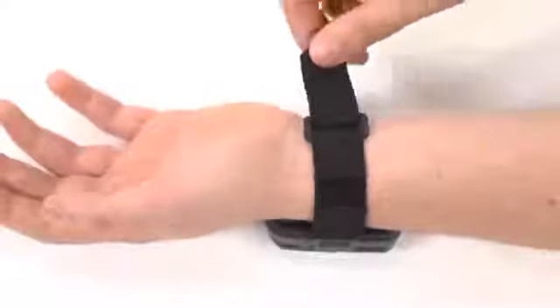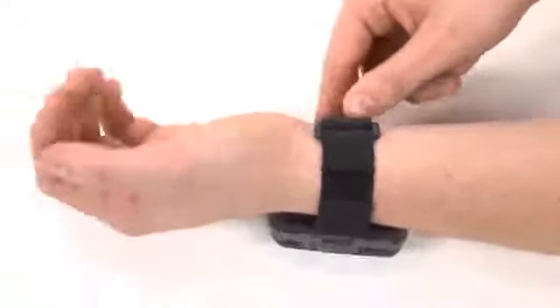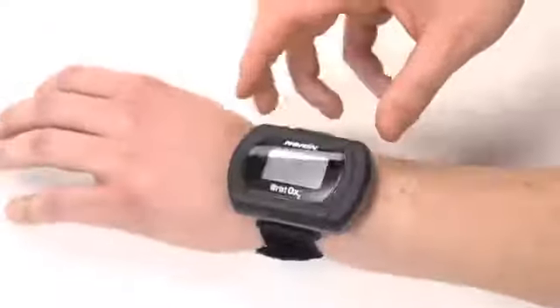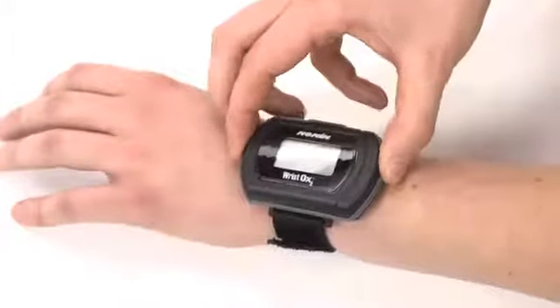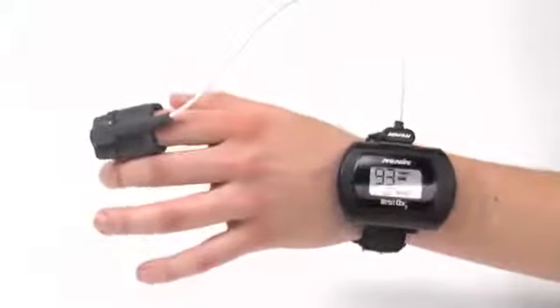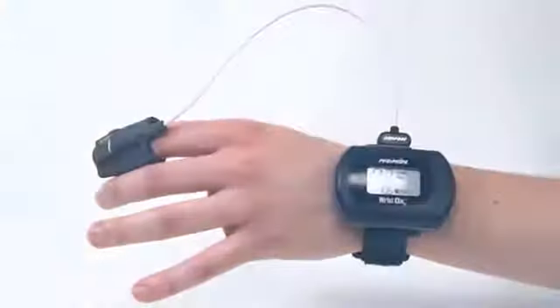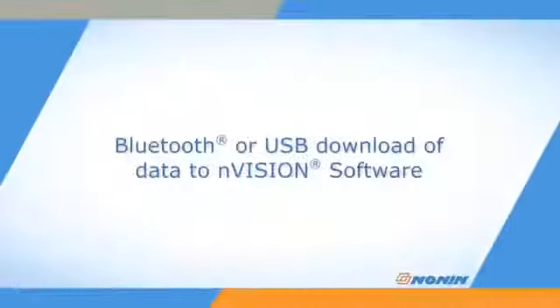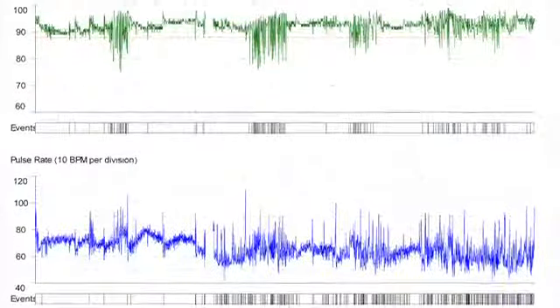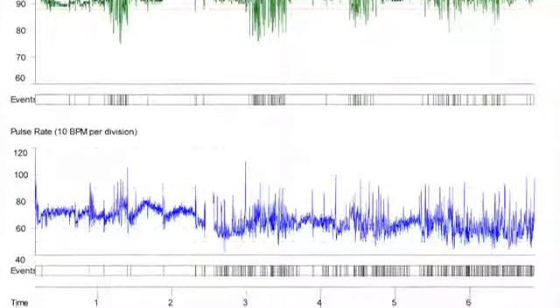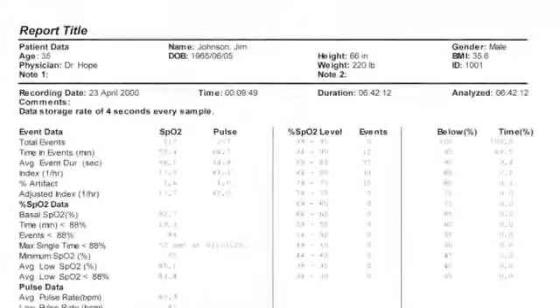Place the WristOx2 oximeter on the patient and check for fit. It should fit comfortably like a wristwatch band. Don't over-tighten. The WristOx2 oximeter is an excellent choice for mobile uses. The WristOx2 can use Bluetooth or a USB cable port for connection to a PC to download recorded oximetry data from memory to nVision. The oximeter can use NONIN's nVision data management software to program settings, modes, and analyze SpO2 and pulse rate data.